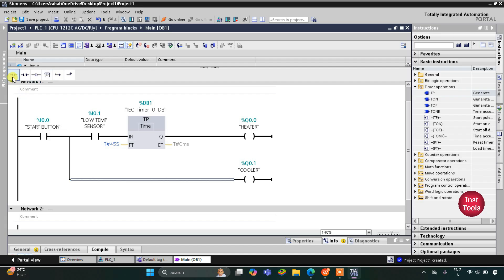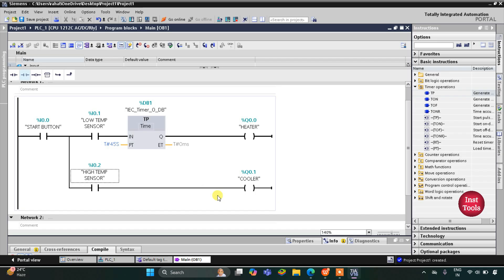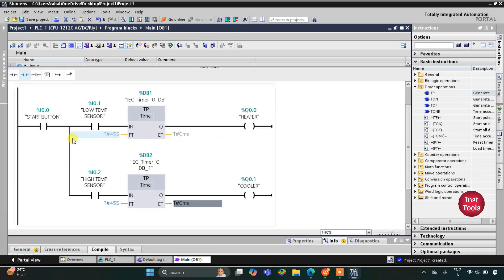Here I will insert a normally open contact for the high temperature sensor. If the temperature is high, the cooler will turn on and remain on for 45 seconds. For that I will insert a TP pulse timer with a preset value of 45 seconds. So when the start button is on, if the low temperature sensor detects low temperature, the heater turns on for 45 seconds; if the high temperature sensor detects high temperature, the cooler turns on for 45 seconds.